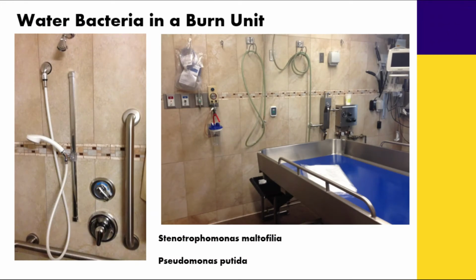This is a situation where there was a construction project across the street from a hospital that had a burn unit, and this is the burn unit's system that they had. And those hoses that you see dangling were heavily infested with bacteria that came from the municipal water system that was right beside where they were building a brand new stadium. And the outages and the connections that were made caused contamination. I collected that water, demonstrated where the bacteria came from, and contaminated these hoses.